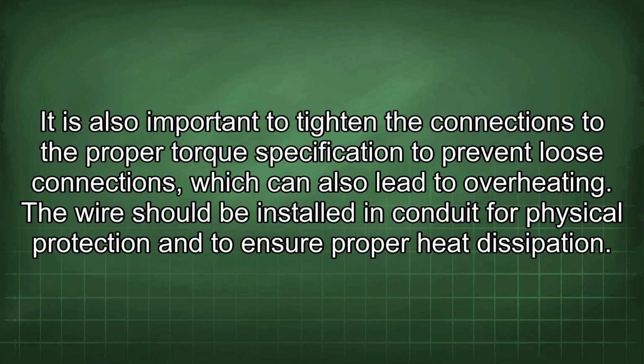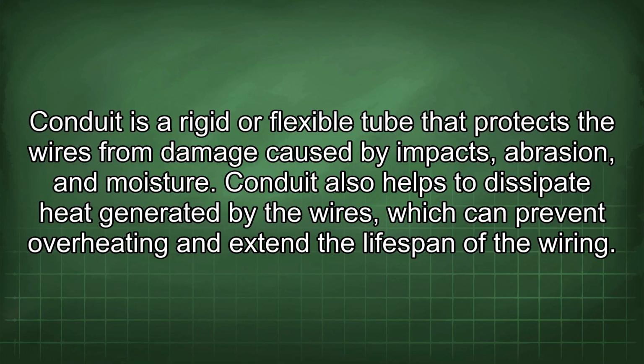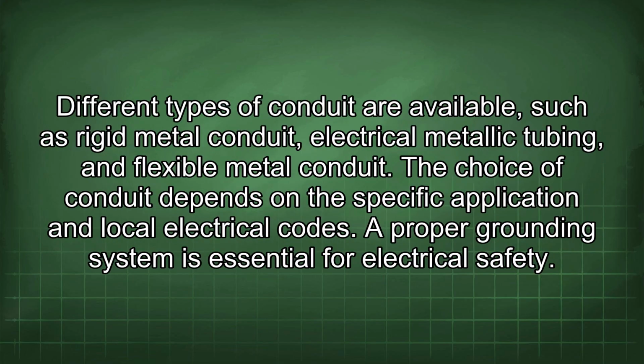It is also important to tighten the connections to the proper torque specification to prevent loose connections, which can also lead to overheating. The wire should be installed in conduit for physical protection and to ensure proper heat dissipation. Conduit is a rigid or flexible tube that protects the wires from damage caused by impacts, abrasion, and moisture. Conduit also helps to dissipate heat generated by the wires, which can prevent overheating and extend the lifespan of the wiring. Different types of conduit are available, such as rigid metal conduit, electrical metallic tubing, and flexible metal conduit.